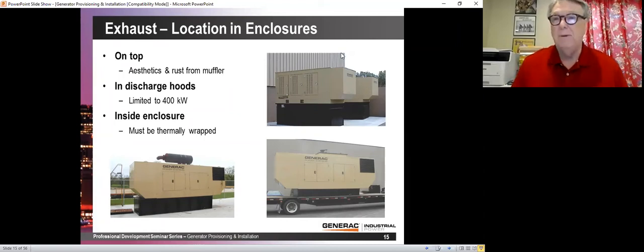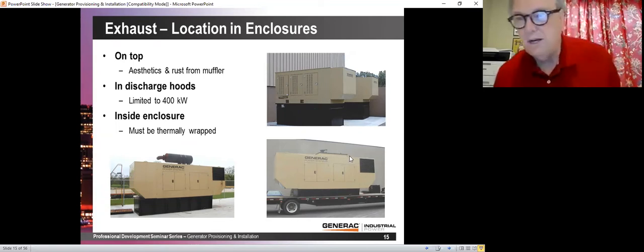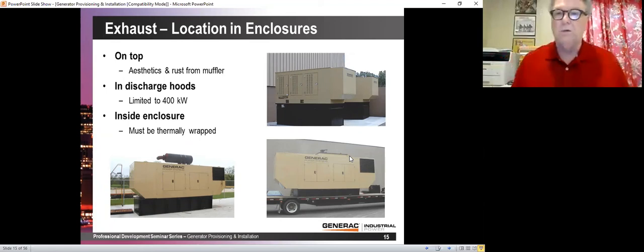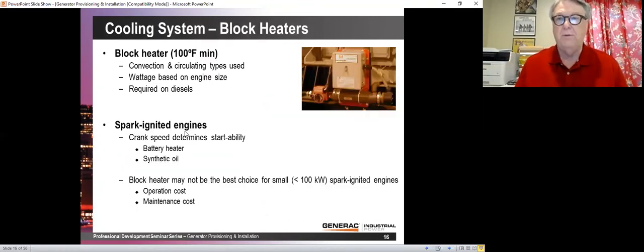Typically with today's EPA engines and this type of system, you won't even see any smoke that was so common in years past. This is called a nested muffler on the bottom. It's a design that is available in some generators, particularly the large ones. In this case, the silencer or the muffler is rectangular, and it stands, roughly maybe a third above the generator, and then the other two-thirds is down sitting inside the generator enclosure, which is why we call it a nested muffler. It's kind of nested in that enclosure. Anything inside the enclosure for exhaust should be thermally wrapped, and the generator manufacturer will always do that.